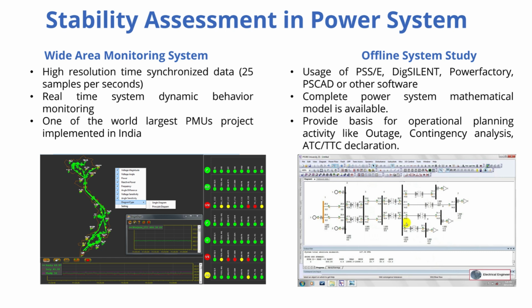And the final tool mentioned is WAMS, Wide Area Monitoring System. The key features highlighted are high-resolution time-synchronized data and real-time system dynamic behavior monitoring. What's special about WAMS? WAMS uses PMUs, phasor measurement units. Unlike SCADA's slower updates, PMUs measure voltage and current phasors, magnitude and angle, very rapidly, maybe 25, 30, 60 times per second. And crucially, they are precisely time-stamped using GPS. So you see things happening simultaneously across the whole grid. Exactly. You get a high-fidelity, time-synchronized view of the grid's dynamic behavior in real time.